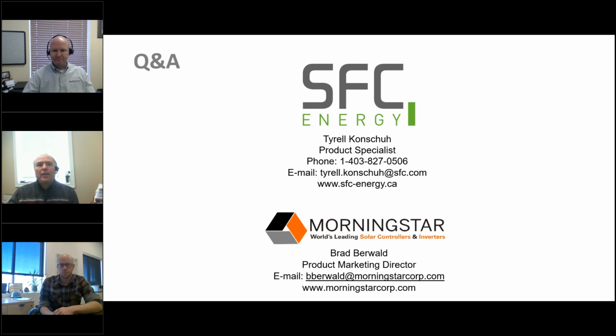Anything to add, Ty? Not really on my end. Essentially our unit behaves differently than solar in this regard, because it detects the battery bank voltage and charges accordingly, distributing its charging current at that voltage and whatever current is needed. It charges similarly to a solar array, going through a bulk charge at high current and then an absorption stage at lower current. So while I can't give quite the same answer as Brad, typically our unit automatically charges the batteries in a similar way.